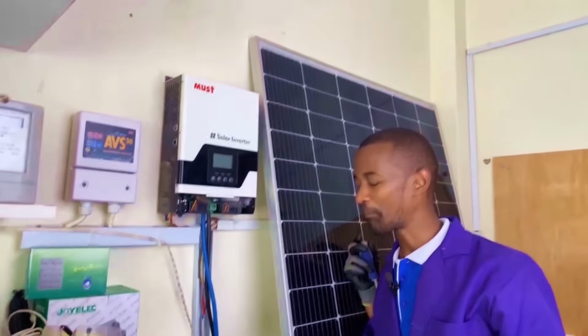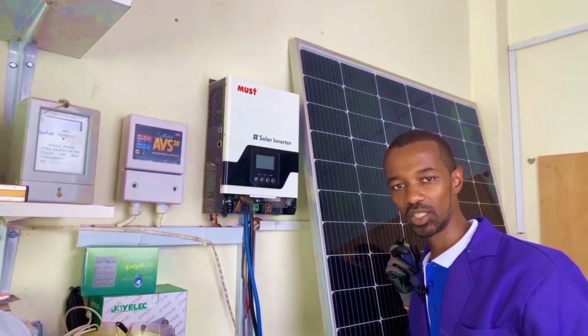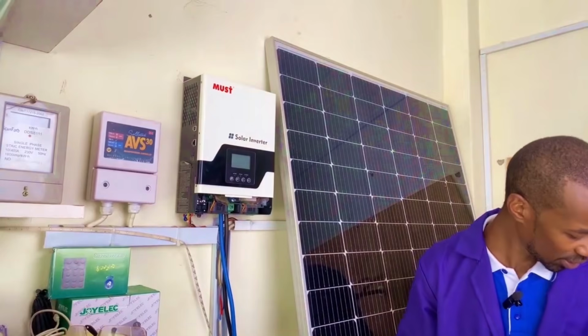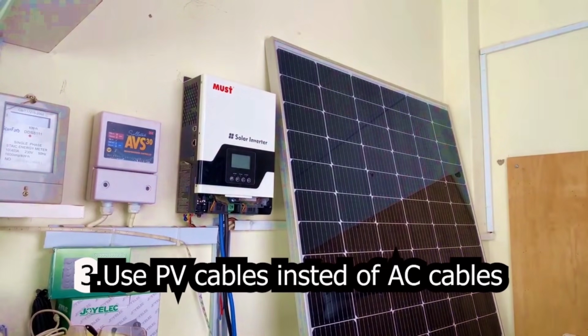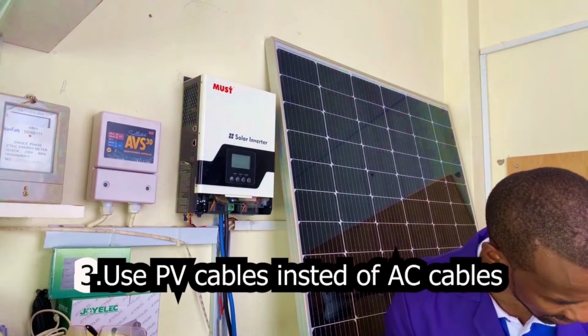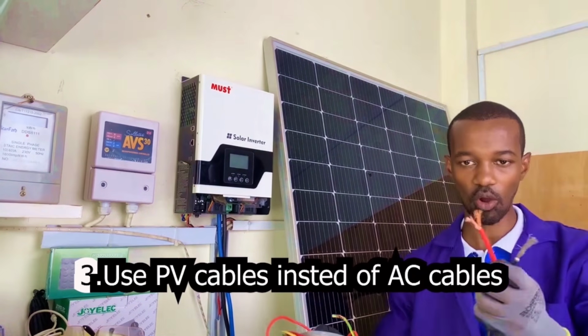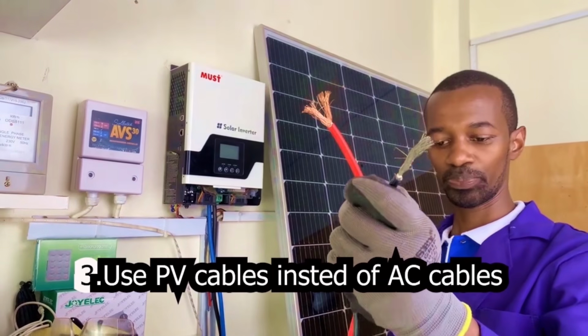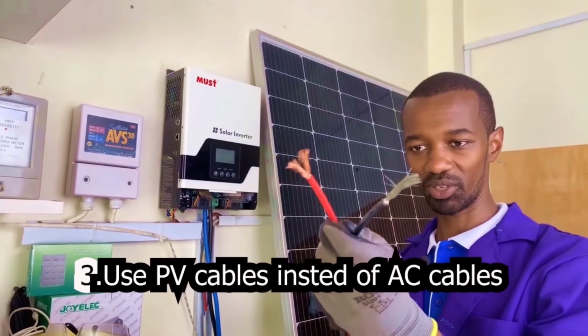Now, my top boss, mistake number 3 is using the wrong cables. For instance, I've been fighting a lot with many electricians whereby they prefer to use these cables, which are AC cables, instead of using these cables, which are referred to as PV cables.